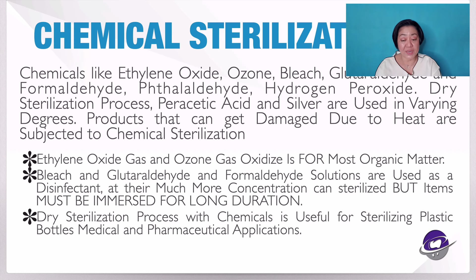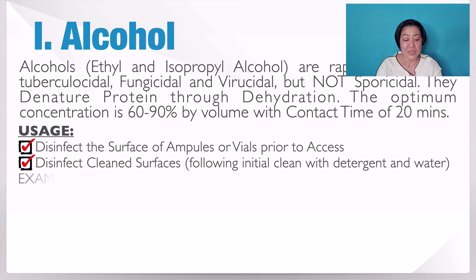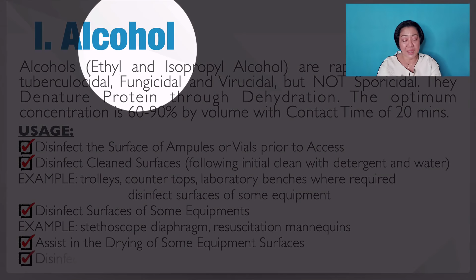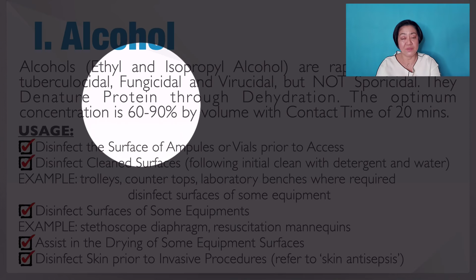Glutaraldehyde, for example, became so popular a long way back. But the problem is that it damages the metal alloys of our instruments. But with chemical sterilization, as long as you allow the instrument or the surface the proper duration of time, direct contact, and proper concentration, it works very well. Like, for example, alcohol, which went out of stock during the entire period of COVID-19. As I've said, alcohol needs a contact time of 20 minutes and a concentration of at least 70% to be effective.